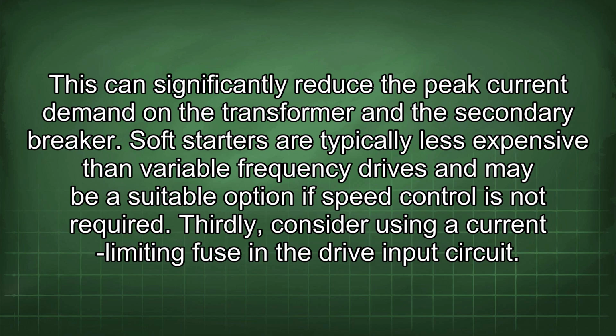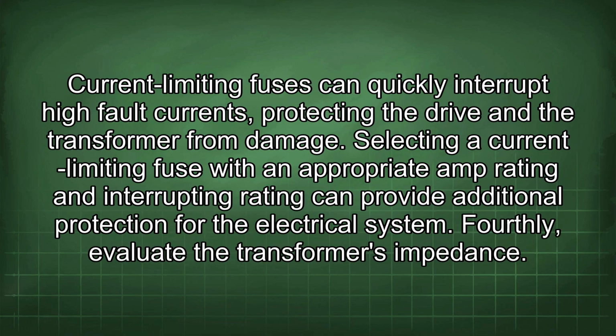Soft starters are typically less expensive than variable frequency drives and may be a suitable option if speed control is not required. Thirdly, consider using a current limiting fuse in the drive input circuit. Current limiting fuses can quickly interrupt high fault currents, protecting the drive and the transformer from damage. Selecting a current limiting fuse with an appropriate amp rating and interrupting rating can provide additional protection for the electrical system. Fourthly, evaluate the transformer's impedance.